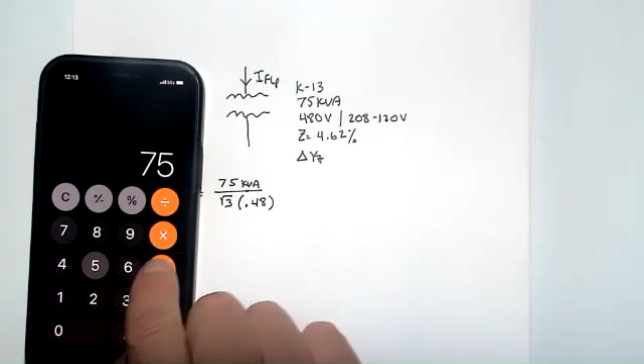Remember what I told you earlier? 75 times 1.2. Oops, divided by: 75 times 1.2 is 90 amps. So we end up with 90 amps, which is that 1.2 multiplier when you have a 480 volt system. Now here's the cool thing. If I want to calculate I full load secondary, I know it's 208 amps.